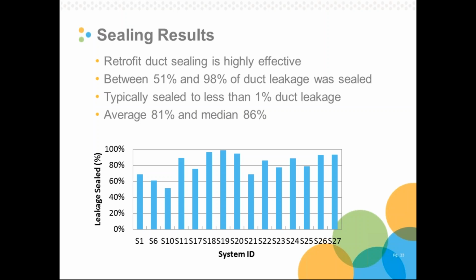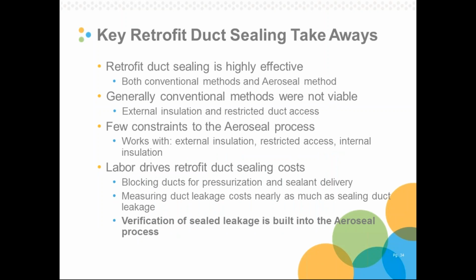And we definitely saw that these numbers were going up in time as we worked with our contractor, who was new to this process, and they developed expertise on this sealing work. So to reiterate, retrofit duct sealing is highly effective with all types of measures, both conventional methods and Aeroseal methods. However, except for a few systems, we were essentially prevented from pursuing conventional methods for duct sealing. This was mainly due to external insulation and restricted duct access. A majority of our systems were insulated from the outside, and that drastically limited the options. So we were left with a choice to pursue aerosealing exclusively or specifically seek out systems that could be retrofitted with conventional methods, and we pursued the latter. It was a lot easier to aeroseal these systems.